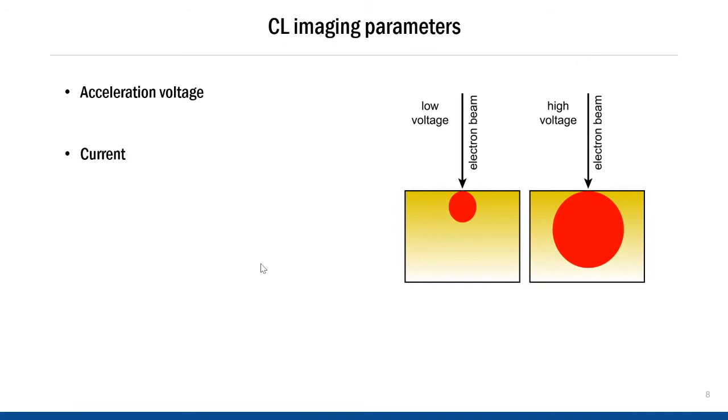Next parameter is the beam current. Is it always best to use a high current? Sending in a high current is good because it will generate more CL signal, but too high a current may result in charging. Also, a higher beam current means a larger spot size, so there's also the risk of losing some spatial resolution. So should you always use low current? It's true that the spatial resolution would improve if you lower the current and therefore the spot size, but a lower current also means a lower signal and more noise. You would need longer acquisition times to get enough signal, and that's why you need to strike a balance for a given sample.